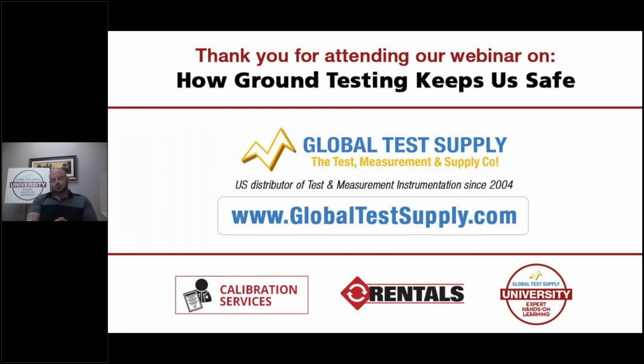Very good, one of the most to-the-point questions anybody could ask. You can wet the probes. The test probes are not part of the measurement, but they do have to meet a certain parameter. Now, the parameter is quite high — on our testers it's up in the thousands of ohms. But nonetheless, the probes do have to make enough contact with the surrounding soil to make their measurement. So to do that, yes, you can most certainly wet them, and that's an effective technique. It does not affect the measurement.